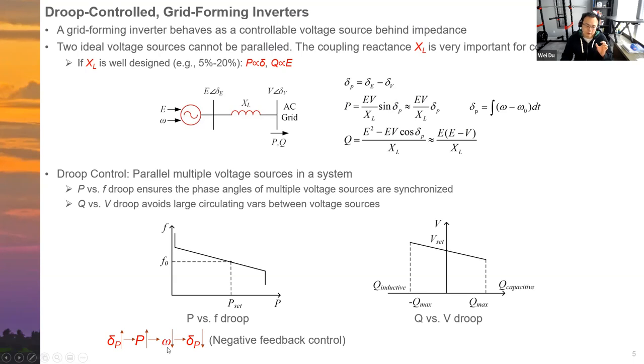And because the phase angle is the integration of the frequency, if you reduce the frequency, the phase angle will also be reduced. So once a disturbance causes the phase angle to increase, the droop control eventually prevents the phase angle from increasing further. This is a very simple negative feedback mechanism that assures multiple grid forming inverters can work in parallel and maintain the synchronism of their phase angles. Similarly, the QV droop control also tries to avoid large circulating reactive power between these voltage sources.